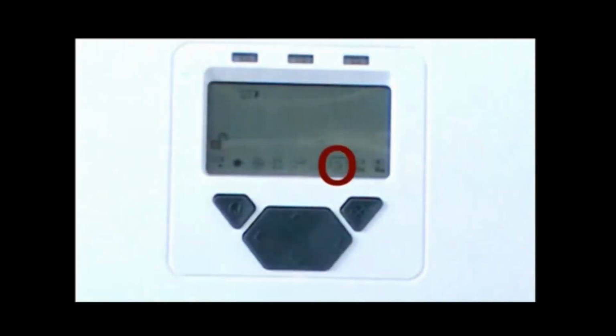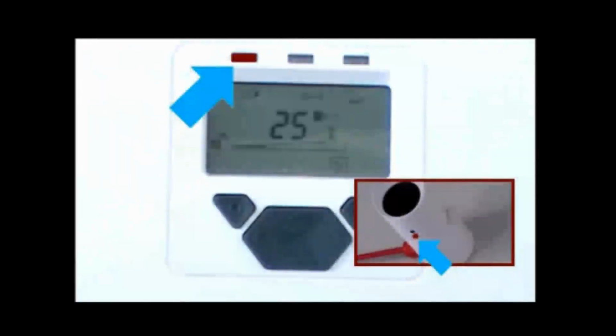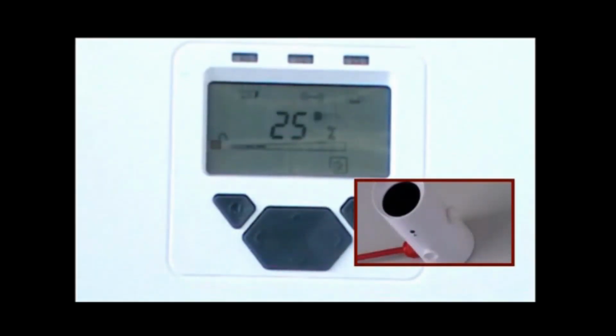Now it is time to conduct a fire and fault test to confirm correct commissioning. A remote fire test is performed by selecting the remote fire test icon, third from right. Press Tick once to test the fire LED on the underside of the receiver. A second tick will simulate a fire condition in order to test the relay and wiring back to the fire panel. The display will show fire, and the fire control panel should indicate a fire condition. The system controller LED corresponding to the receiver under test will flash red.